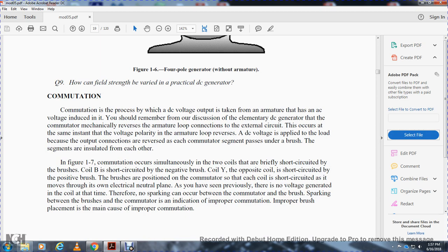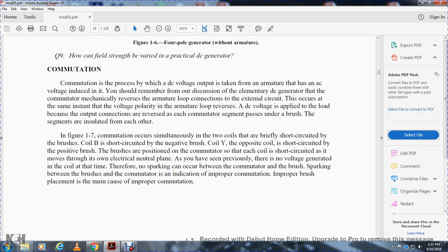Commutation: commutation is the process by which DC voltage output is taken from an armature that has AC voltage induced in it. The commutator mechanically reverses the armature loop connections to the external circuit at the same instant the voltage polarity in the armature loop reverses, so DC voltage is applied to the load. Each commutator segment passes under a brush, and segments are insulated from each other. As shown in figure 1-7, commutation occurs simultaneously with a coil being briefly short-circuited by the brush. The brush is positioned so that each coil is short-circuited as it passes through the electrical neutral plane, where no voltage is generated. Therefore, no sparking occurs between the commutator and brush. Sparking between brushes and commutator indicates improper commutation due to improper brush placement.